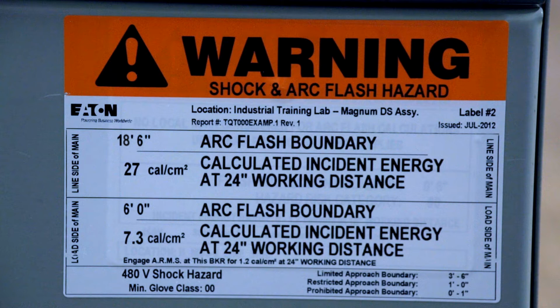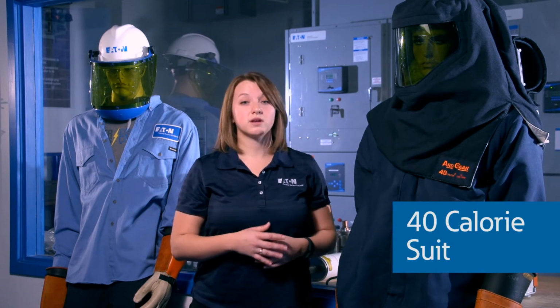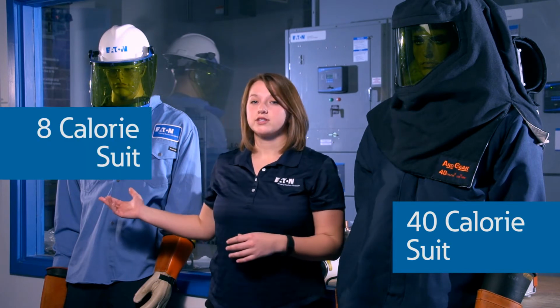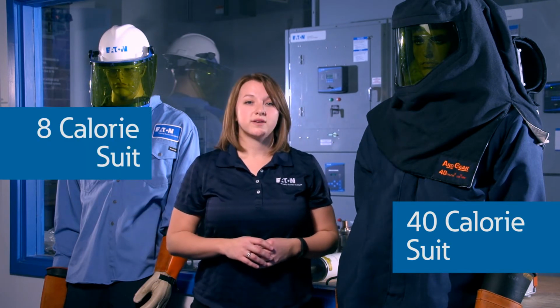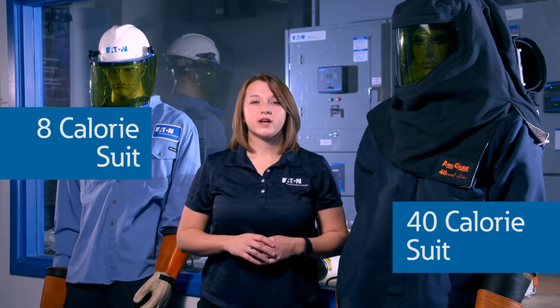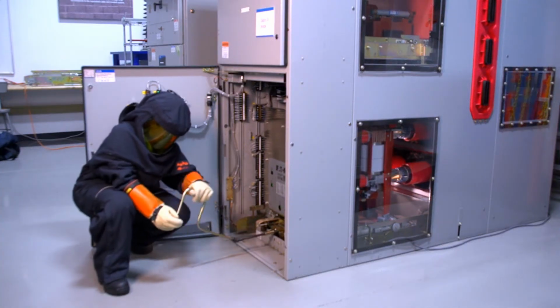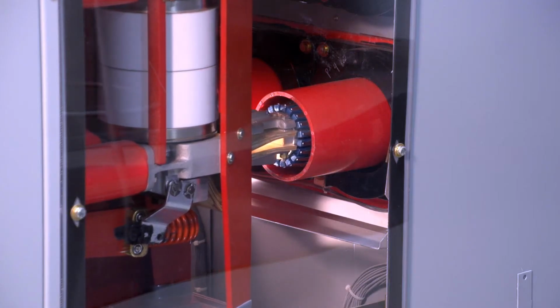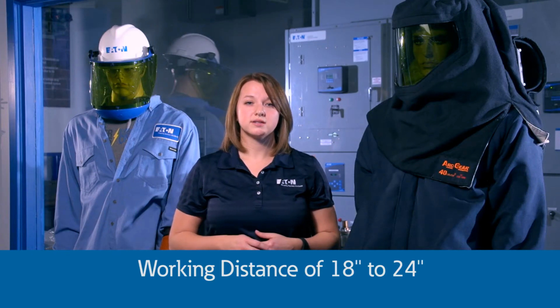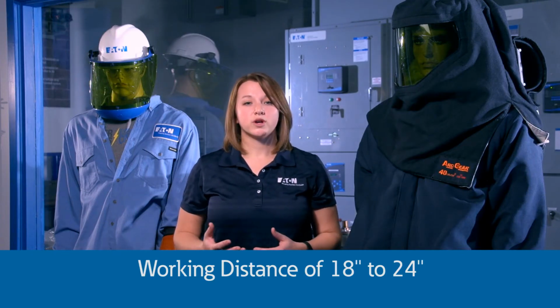This arc flash label indicates that the arc flash energy is 27 calories per centimeter squared. So in order to protect a worker from this amount of energy, they would have to wear a 40-calorie suit, like this one. A worker dressed in an 8-calorie suit would not be protected from a 27-calorie event. The clothing effectively acts as a thermal barrier to the arc flash event, protecting the worker from the thermal energy at a working distance of typically 18 to 24 inches.